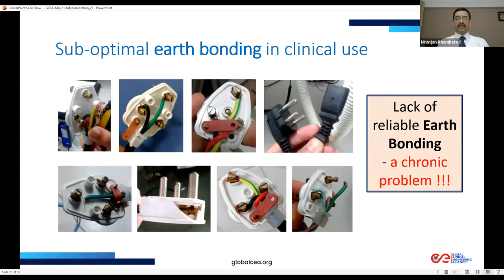Typically, I have seen in many hospitals that when it comes to use of clinical equipment, because it is handled, because the 3-pin plugs are wired on their own, maybe not as per correct guidelines, maybe the manufacturer quality isn't good enough, you find there is always some compromise or suboptimal earth bonding of the equipment in clinical use.